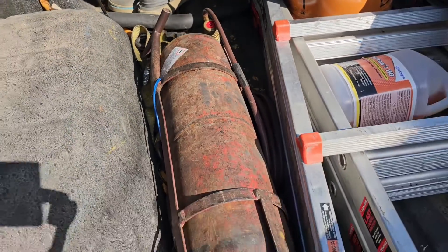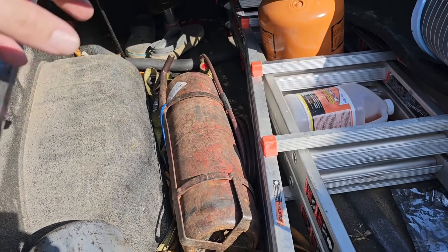Advantages and disadvantages of Ambro Controls OxySet. Advantages: it's very light. I'm always looking for tools to make my job easier. When you do a couple coil changes a day or compressor changeouts, you've already got heavy tools like your nitrogen tank, vacuum pump, or recovery machine. It's nice to have torches that aren't loaded down like a regular turbo torch or oxy-acetylene torch. Disadvantages: I don't really see any. You may have to carry a couple extra tanks because the tanks are really small and you may run out. But with regular oxy-acetylene torches I always carry extra backup tanks anyway. I always carry a turbo torch on the service vehicle just in case I have to braze any larger pipe sizes like inch and an eighth.